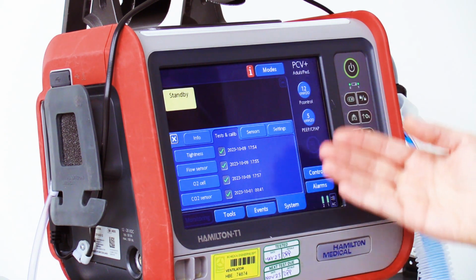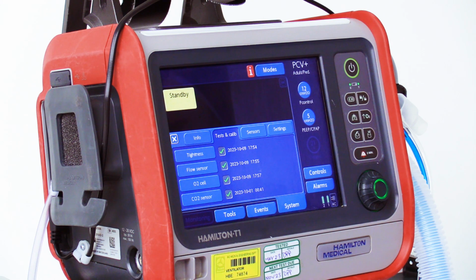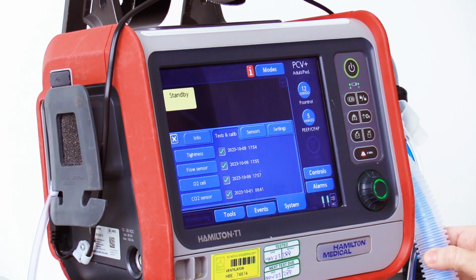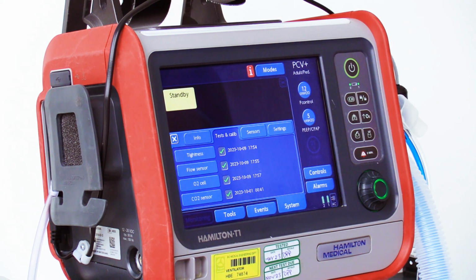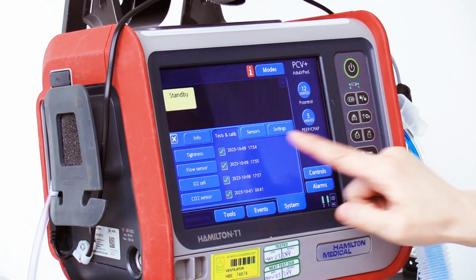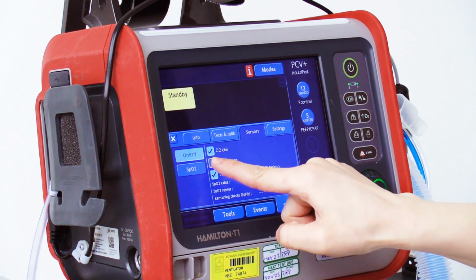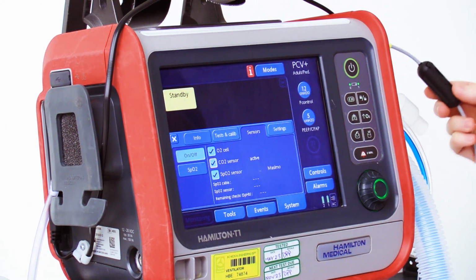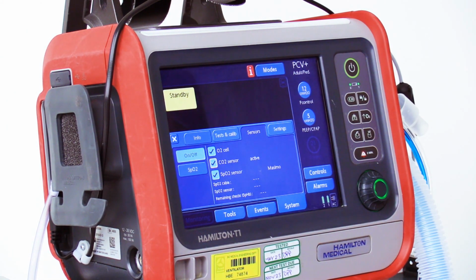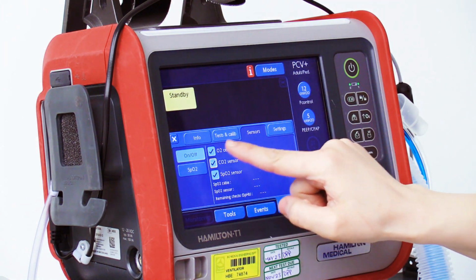Make sure you do the leak test and calibrate the flow sensor before connecting a new patient to the ventilator, and after you've connected a new breathing circuit or any other new component. Go to the Sensors tab and make sure CO2 monitoring is enabled if you want to monitor CO2. If it is disabled, you will not be able to calibrate the CO2 sensor.